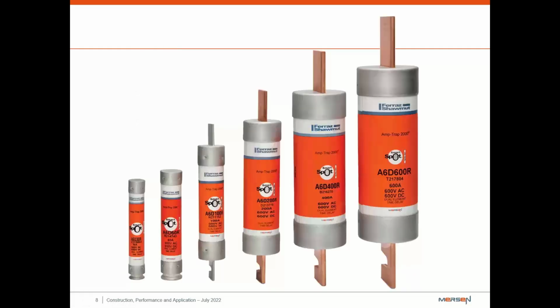One of the engineering mitigation factors that we also use is rejection by size. So as the ampacity goes up, and this kind of makes sense after we go through the construction, the fuse body gets bigger. So when the body gets bigger, it goes into a different holder. So it'll restrict the end users from putting the wrong ampacity into the wrong holder. But you know, there's still misapplications out there. It can still be done through, you know, street engineering, but this is just something that we do for our end users so that they'll be more protected in the field.